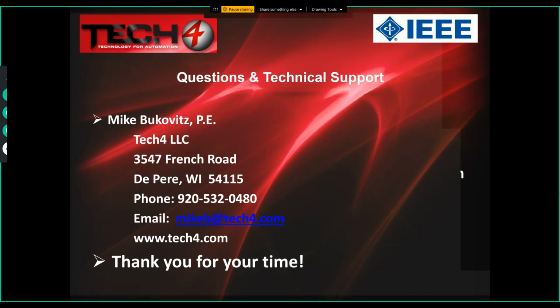The greatest probability of creating any type of unexpected event is when the equipment is being interacted with. That's openly recognized in black and white by NFPA 70E. It's when we interact with the equipment that the risk is highest. So when the risk is highest, we engage a maintenance switch, which overrides protective device coordination when we need it most. Our argument is, for any customer interested in a maintenance switch, talk to them about zone selective interlocking instead. ZSI is wonderful. It works. It's proven. It shouldn't cost much more to implement than a maintenance switch. Probably comparable, might be slightly more expensive, but you always maintain protective device coordination.